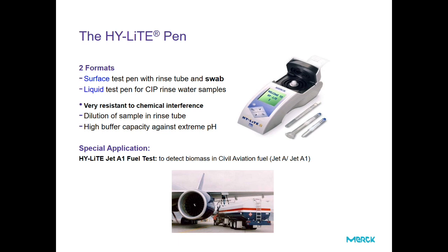For collecting samples and running the bioluminescence reaction, we have consumables called HY-LiTE pens. We have two formats of the pens. We have a surface test pen, which comes with the swab and the rinse tube for swabbing the surface and extracting the sample into the rinse tube. And then we have a liquid test pen dedicated to testing cleaning-in-place solutions for the presence of ATP. These consumables are very resistant to chemical interference, providing dilution of the sample in the rinse tube and a high buffering capacity against extreme pH.